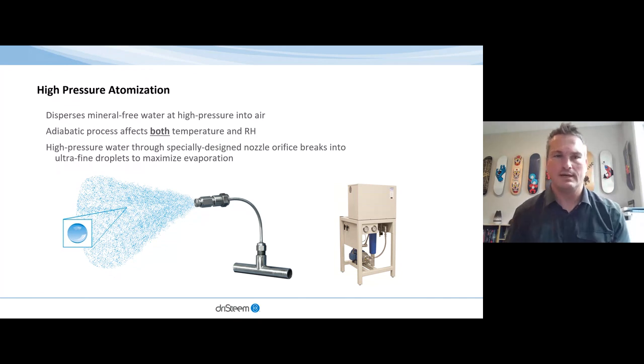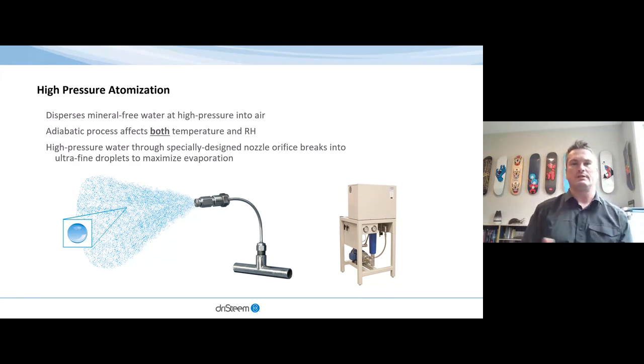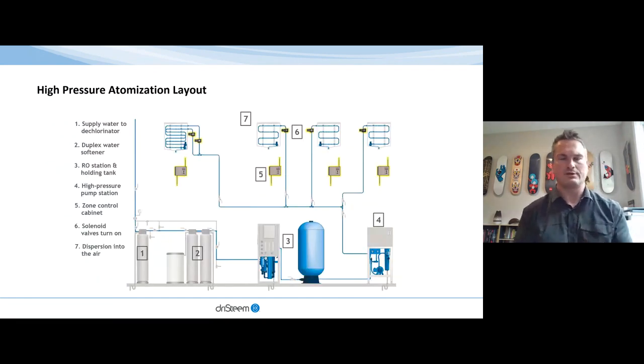High pressure atomization is dispersing mineral-free water at high pressure within the air handler or the ducted system. Again, that high pressure water through an orifice or a nozzle breaks the surface tension and provides both the cooling of the temperature and the relative humidity. The benefit of high pressure over media evap is its ability to be controlled very tightly, so the output can be controlled in this type of setup. However, there's a lot more infrastructure involved typically with high pressure atomization versus media evap.